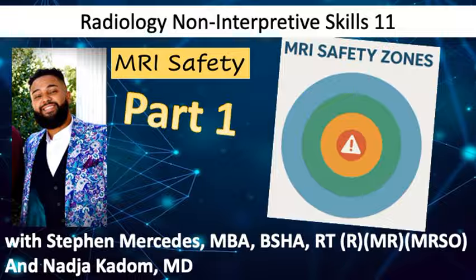Yeah. And that's something that if you don't know, you don't know. A lot of the people in the MRI environment assume that whatever's in the room is safe. That's where we have the categorization of safe, conditional, and unsafe. Unsafe, it's not going into the room. MRI conditional is where a lot of our equipment falls, even the MRI scan tape, the one that actually docks onto the table, is labeled as conditional. The reason is that if you put it through a ferromagnetic detector, it will alarm because there are little bolts and screws well embedded in there, but they are there. So it's not necessarily MRI safe unless it's totally plastic.